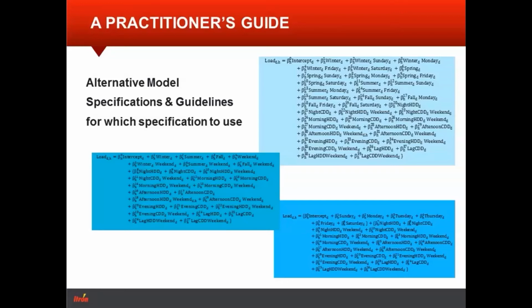So you can get there very quickly, 90% of the way, but that last 10% takes a lot of hard work and requires focusing on very specific days or periods of time in your load history and trying different explanatory variables to improve that particular period of time. For example, you may have a full-blown extended day type with temperature splines, or even a neural network, but it's not hitting your peak days. And you would focus on just those peak days and what it was about the weather leading into that peak day that your base equations just aren't capturing.